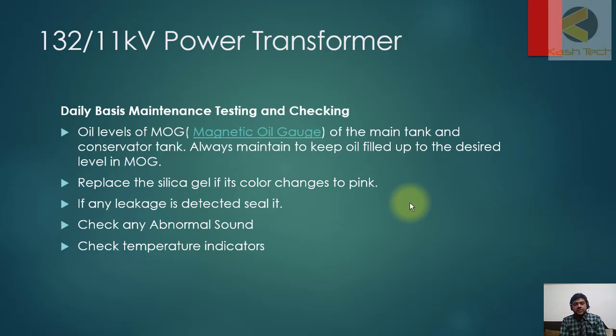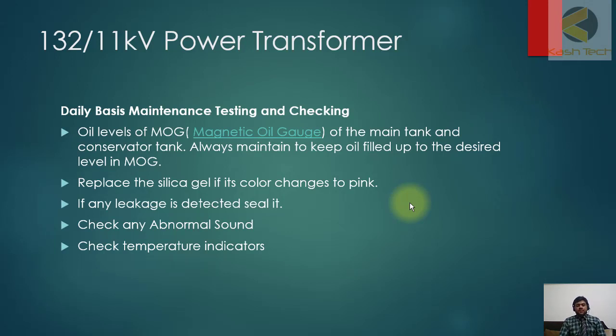If any leakage is detected, that is another common issue to look for. Normally stones are placed under the transformer where you can clearly see if there is a slow leakage or seepage. You should also listen for abnormal sounds that might come from vibrations or from the fan. Check temperature indicators — a curve is provided by the manufacturer; check at various load levels whether the transformer temperature is as per the curve. If it's higher, there may be an issue to refer to the manufacturer.